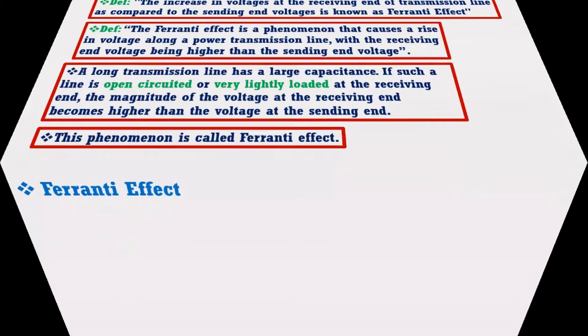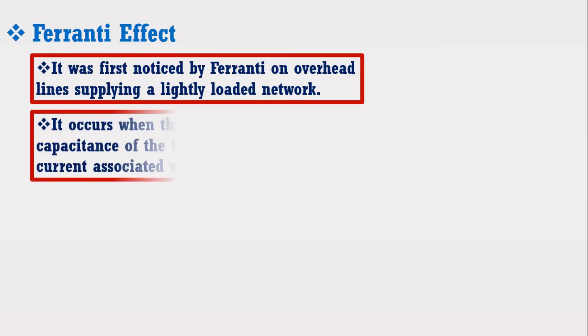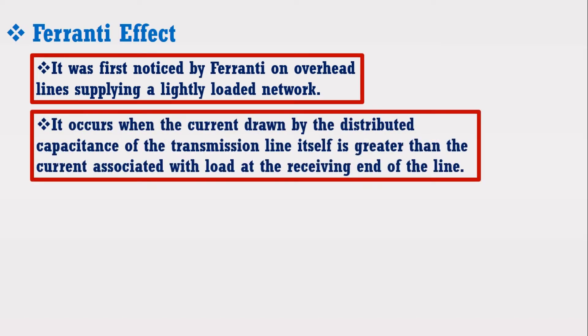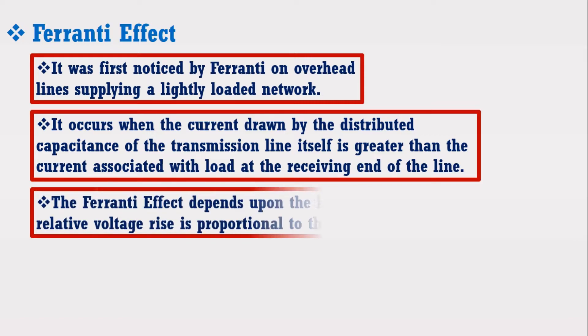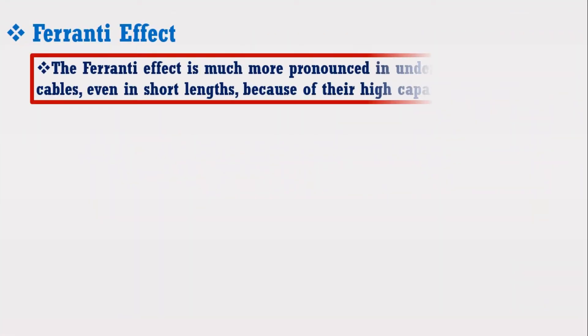It was first noticed by Ferrenti on an overhead line supplying a lightly loaded network. It occurs when the current drawn by the distributed capacitance of the transmission line itself is greater than the current associated with the load at the receiving end of the line. The Ferrenti effect depends upon the length and voltage applied, and the relative voltage rise is proportional to the square of the line length.